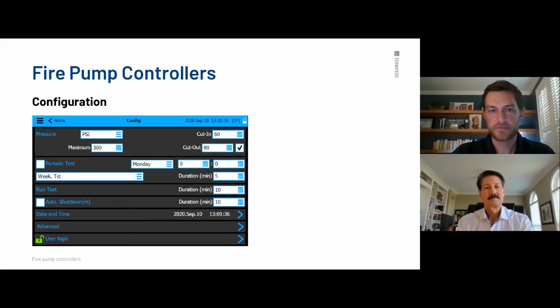There's also this advanced feature, which we're not going to be getting into all the advanced features right now, but advanced is going to be, like I mentioned, where you're going to be doing your alarm testing. And alarms are actually one of the very first things once you go into the advanced segment. Alarms are the very top of that list, and the phase reversal test is going to be the first alarm. I know that's one that a lot of people look for, it's part of the startup process. So it's advanced, alarms, and then it's the very top alarm on there for doing the phase reversal test.